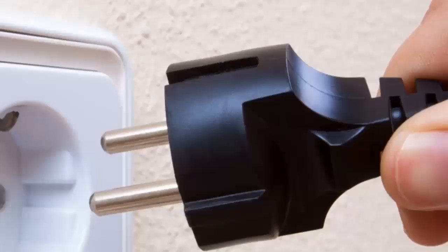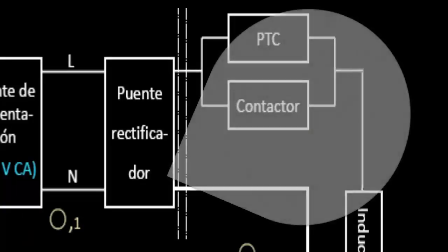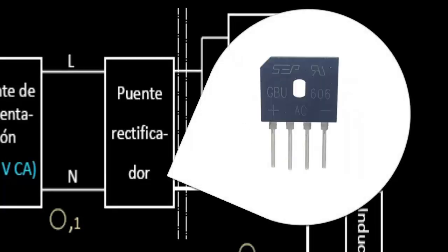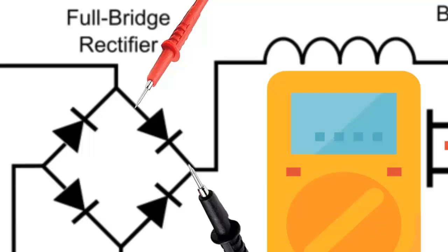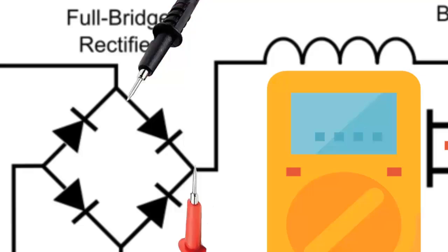Point 3: If the voltage in the previous point is not adequate, disconnect the board and wait a few minutes for the capacitors to discharge. Check each diode of the rectifier bridge. Remember that diodes only allow current to pass in one direction. Replace any damaged diodes or the rectifier bridge if necessary.